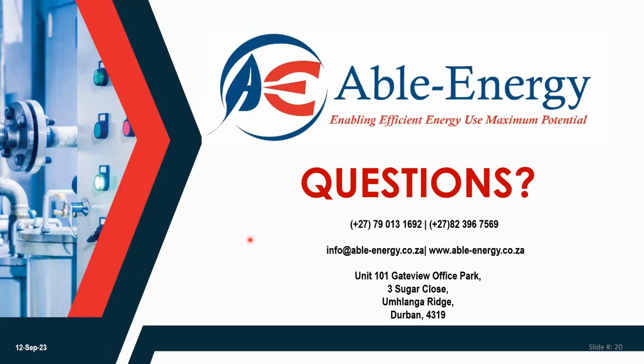Because if you're running a tooling company and the mains goes, your machine needs a bumpless transfer, otherwise all the tools break. Or you've got to say, let's shut everything down because load shedding is happening at 1 o'clock, and then we shut everything down, switch on our standby generators or standby plants, get them running, and then run everything up again. Or do we want a bumpless transfer? So if your mains goes, it switches over to a UPS for 10 or 20 seconds while the standby generator ramps up, and then it goes.